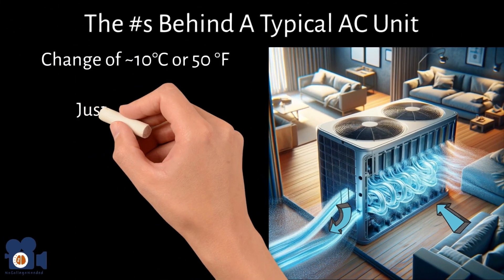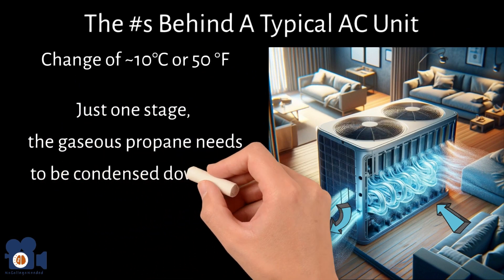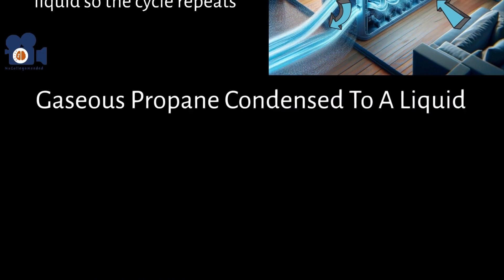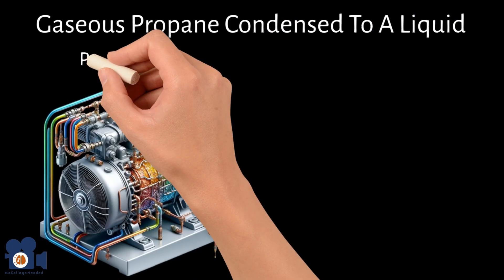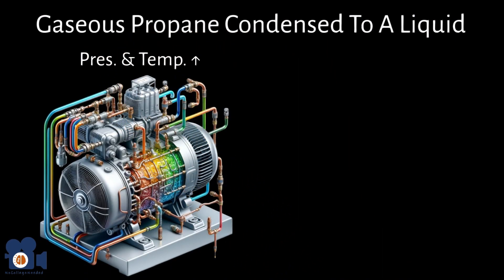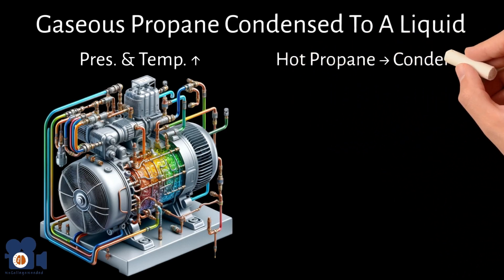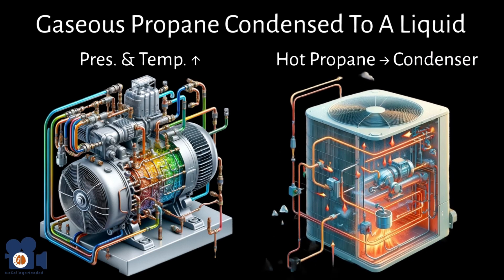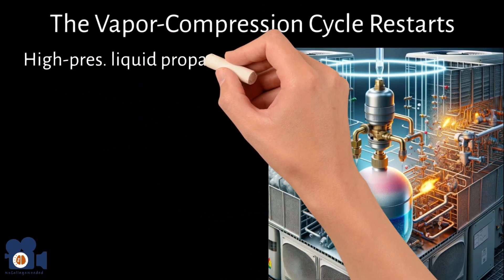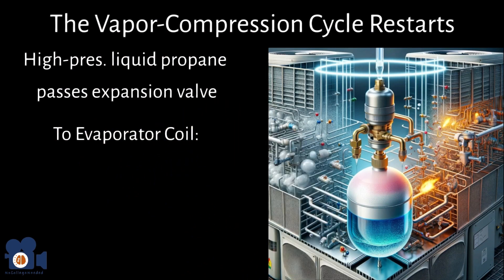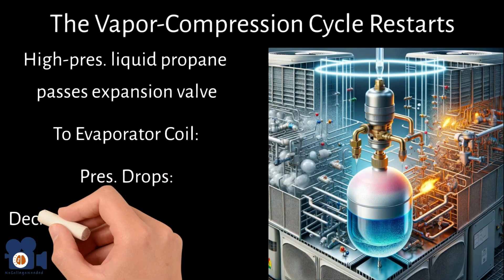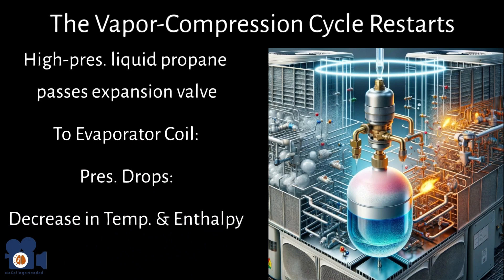Keep in mind that this is just one stage. The gaseous propane needs to be condensed down to a liquid so the cycle repeats. To do this, the vaporized propane is compressed by a compressor, which increases its pressure as well as its temperature, which the AC unit needs to get rid of. To do this, it sends the hot propane to a condenser where the propane transfers its heat to air that is then pumped outside. That is why on any AC unit, there is also a discharge of hot air or the AC unit itself feels warm. From there, the high pressure liquid propane passes through an expansion valve back to the evaporator coil, where its pressure drops suddenly leading to a decrease in temperature and enthalpy to start the cooling process again.